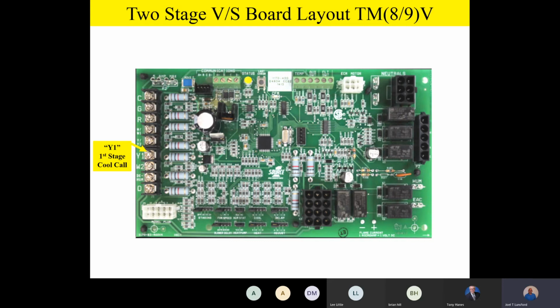So now this control board could actually have 3 fan speed inputs to it: G, Y1, Y2. Well, shucks, I wonder what speed it's going to run at. Remember, team, on any high-efficiency ECM motor, including the variable speed, because it's also a high-efficiency ECM motor, if I have more than one speed command, it always takes the highest speed command priority. So if I have a Y1 and a Y2 and a G call, it's going to drive it to Y2. If I've got a Y1 and a G, it's going to drive it to 65% airflow. If I've got a G-only call, continuous fan, it's going to look at a jumper that we're going to talk about in a little bit, and it'll drive it to that speed.